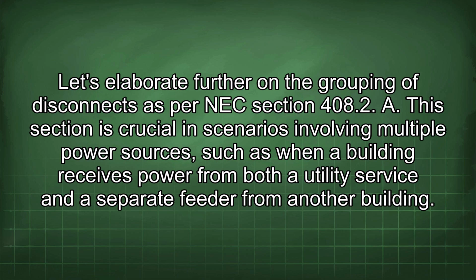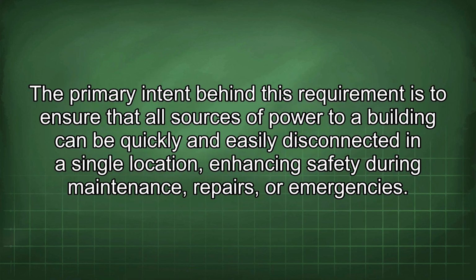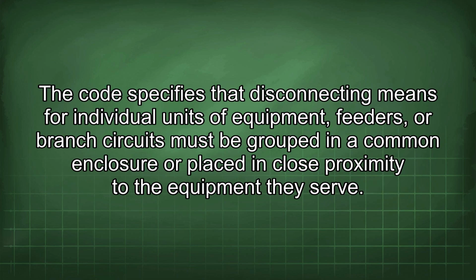Let's elaborate further on the grouping of disconnects as per NEC section 408.2. This section is crucial in scenarios involving multiple power sources, such as when a building receives power from both a utility service and a separate feeder from another building. The primary intent behind this requirement is to ensure that all sources of power to a building can be quickly and easily disconnected in a single location, enhancing safety during maintenance, repairs, or emergencies.